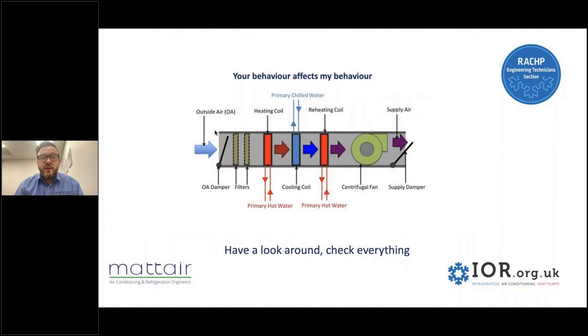So if we flick on to the next one, where your behavior affects my behavior, let's have a look at this air handler. This isn't exactly that air handler, because I didn't have one with a heat exchanger on. It's the only one I could get. The outside air comes in, passes through the first heating coil, which warms the air up, and then it hits the cooling coil. Because it's got a constant heat and cooling load to work against, the chiller is constantly running, counterbalancing the heat that's been brought in through the frost coil. Then the air has been cooled, and it hits the heating coil, which is constantly open and running because the air's cold and it needs warming up. So your behavior affects my behavior because the chiller's running flat out, and so are the boilers. These are the kinds of things that can go unnoticed. Everything may look fine, but just take a closer look.